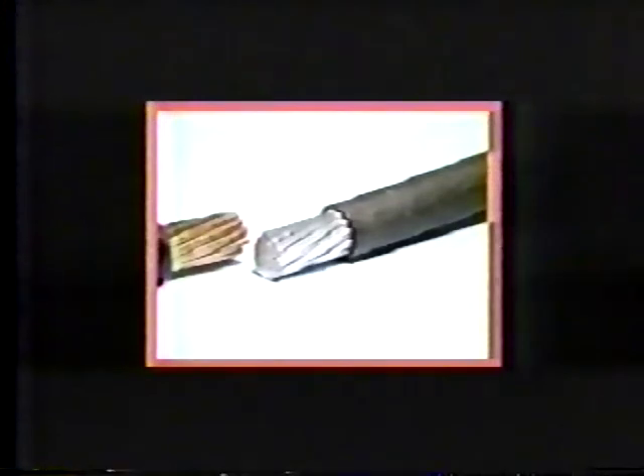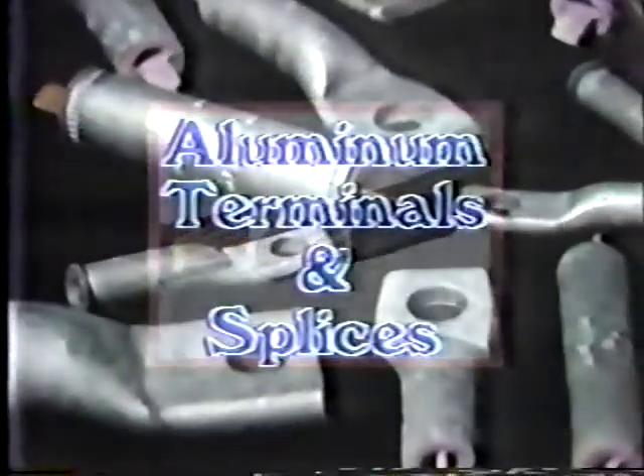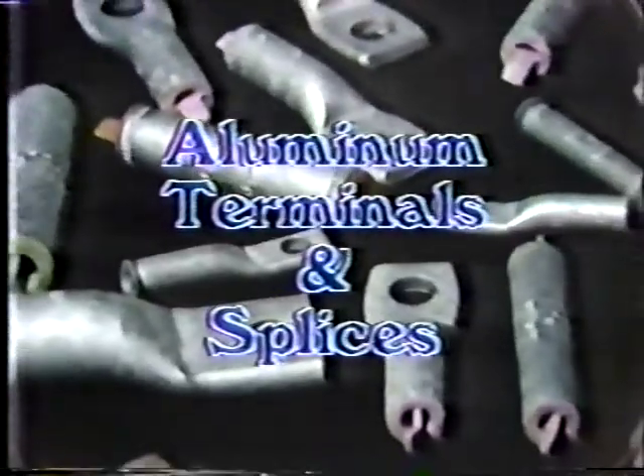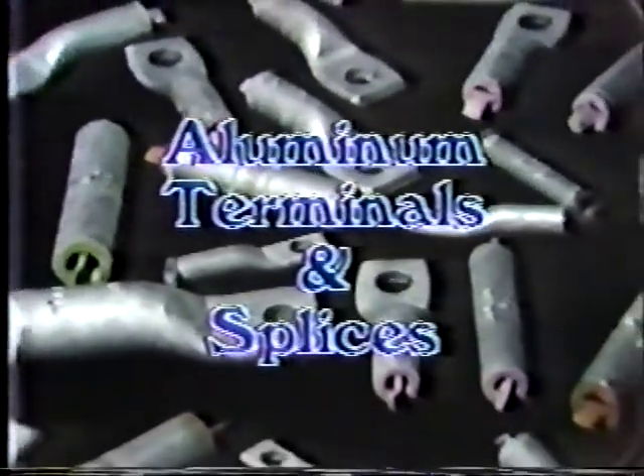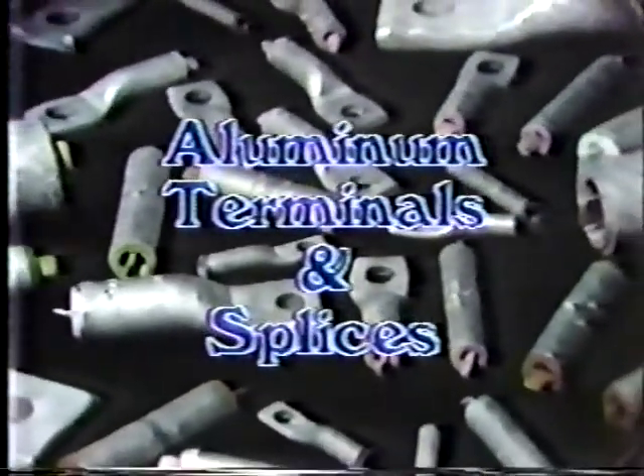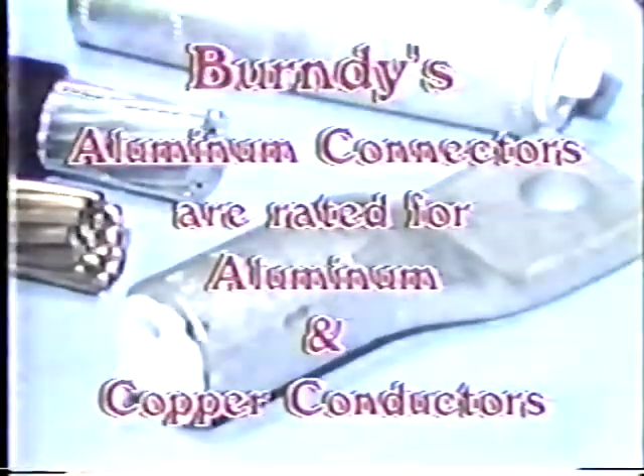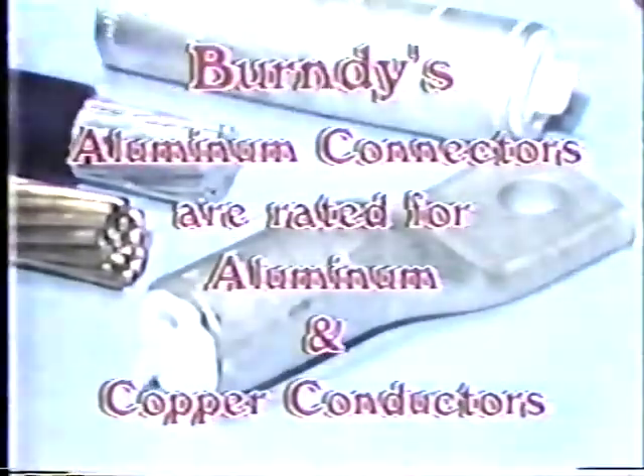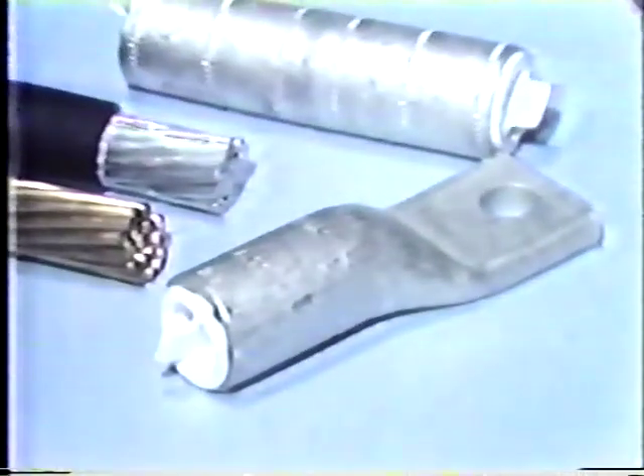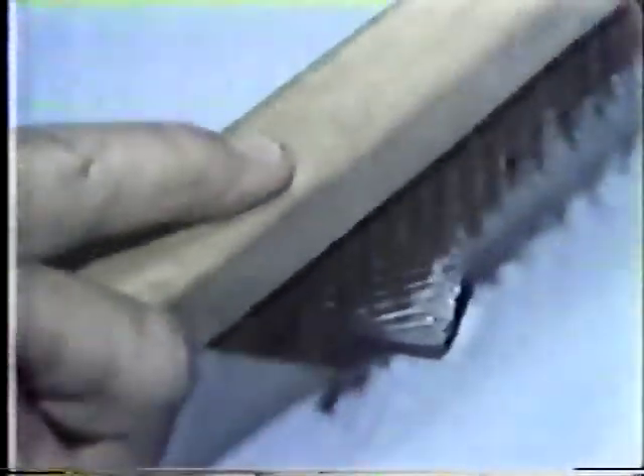Because electrical projects use aluminum conductors as well as copper, Burndy engineers developed a complete line of aluminum terminals and splices, which can be installed with the same installation tools that we've been discussing. In addition, these connectors are rated for use on both aluminum and copper conductors. Although the installation is similar, we strongly recommend wire brushing the aluminum conductor to remove unwanted oxides.